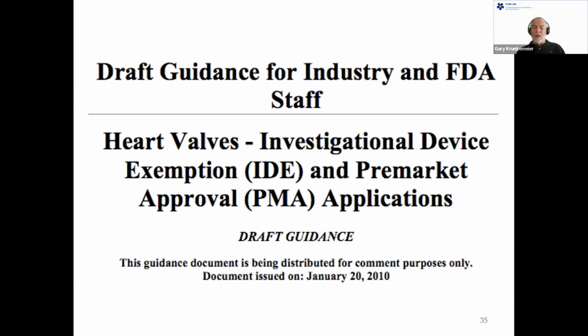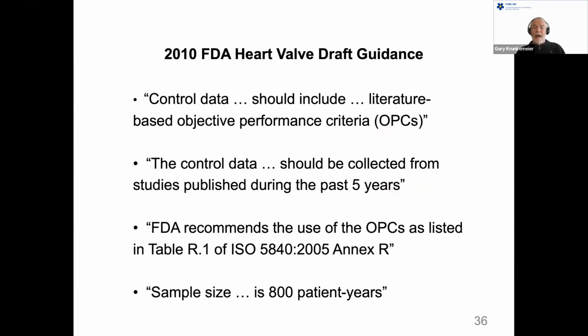Now, in 2010, there was an important draft guidance for heart valves from the FDA, and it simply reiterated that the control data should use the OPCs. They also said the control data should be collected from studies during the past 5 years, and they recommend the OPCs as listed in the ISO document. I don't know why they didn't recommend it as listed in their 1994 document, but they're the same, so I guess it doesn't matter.